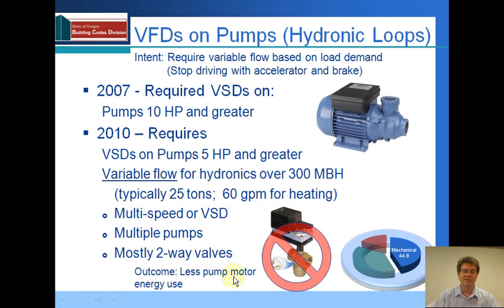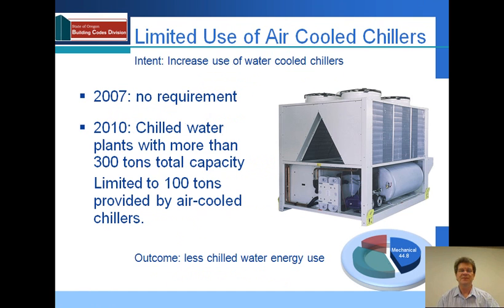Even without a variable speed drive or multiple speed pumps — and the smaller ones don't require that — two-way valves will reduce the flow and reduce the energy use by that pump. Air-cooled chillers are now restricted in use. Water-cooled chillers are much more efficient as they use the evaporative effect of water to cool the condenser water going through the system.